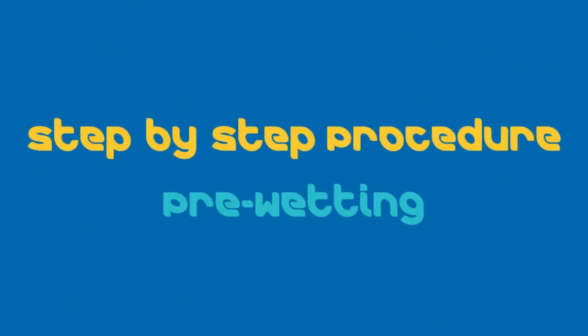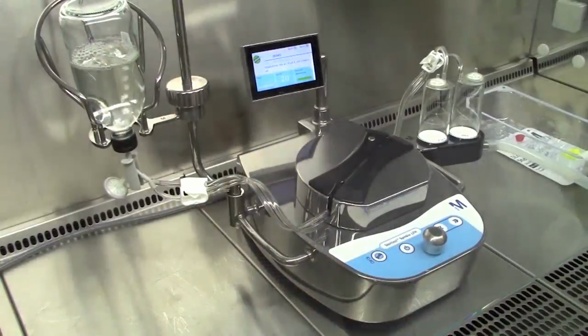At this step, a low speed is recommended to maximize the contact time between the pre-wetting fluid and the filter membrane. Aseptically insert the tube set needle through the septum. Start the pump. Keep the pump running and after a few seconds turn the rinse container upside down and place it in the bottle holder. Allow the transfer of 50 milliliters per canister to pre-wet the filter.